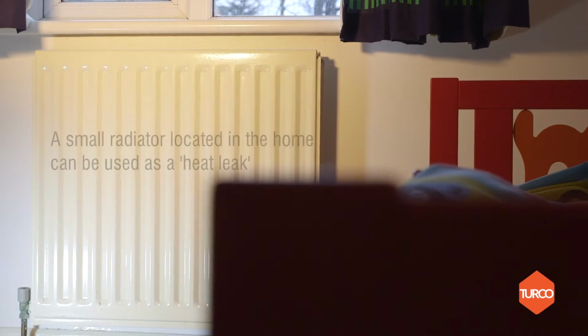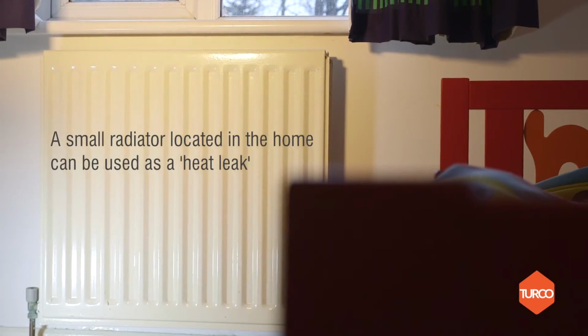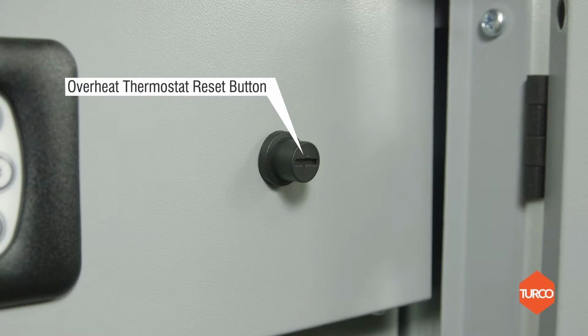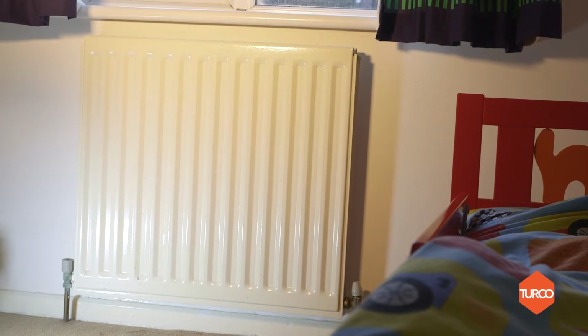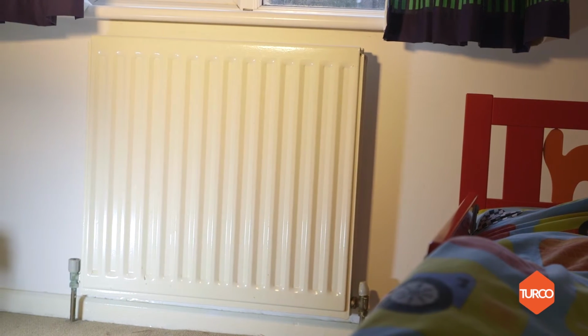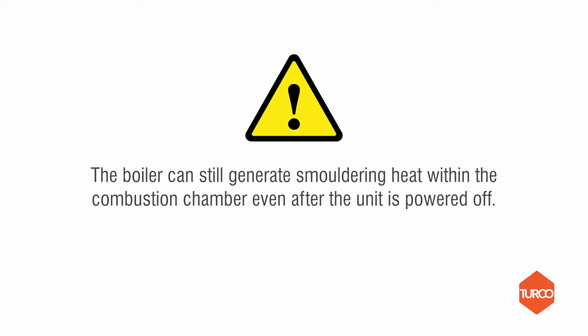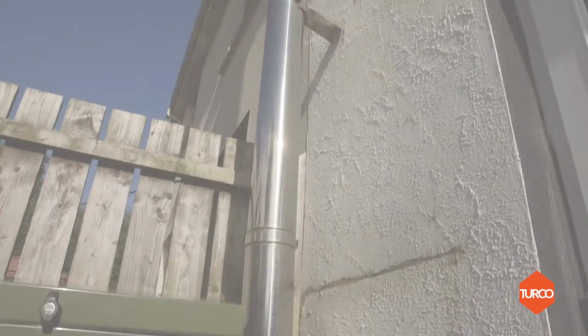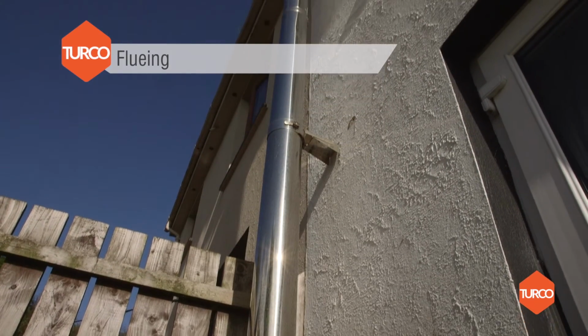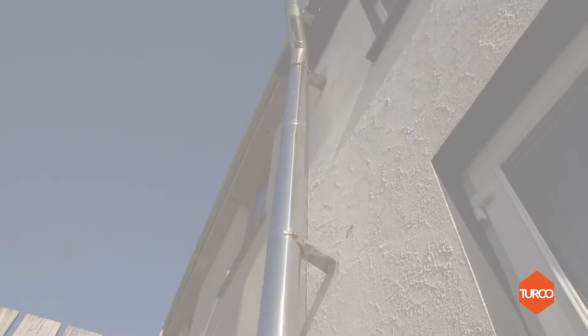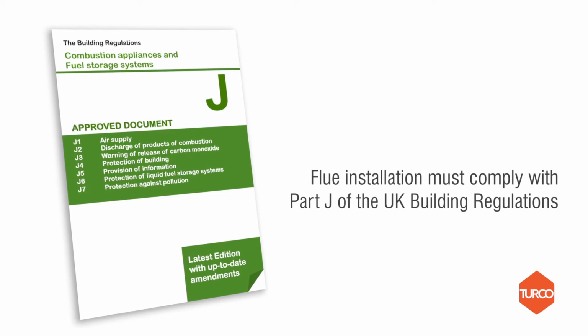It is important that there is sufficient heat leak on the system to absorb any latent heat from the boiler and to prevent nuisance tripping of the boiler overheat thermostat. This is something first-time installers of biomass boilers often overlook. The boiler can still generate smouldering heat within the combustion chamber even after the unit is powered off. Fluing. Fluing of the boiler is an important consideration and must comply with Part J of the UK building regulations.